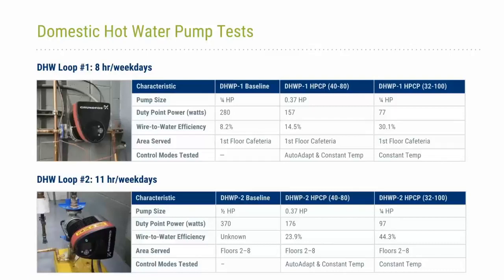But we had a significant increase in wire to water efficiency for the 4080. About halfway through, we replaced the pump with a pump that was more directly sized to the original pump. And you can see that it almost doubled the wire to water efficiency, and we were able to get about a 72% energy savings at full load. So very significant energy savings, even if the pumps were to run at full load. Similar story for domestic hot water pump number 2. You can see very significant duty point power reductions across the board here. The same thing with this one, where we replaced it with the model 4080 and then eventually replaced it with a smaller one. The duty point power savings here was 53% for the model 4080 and then 74% for the other one. So again, very significant energy savings, even if the pumps were to operate at full speed there. Okay, next slide.